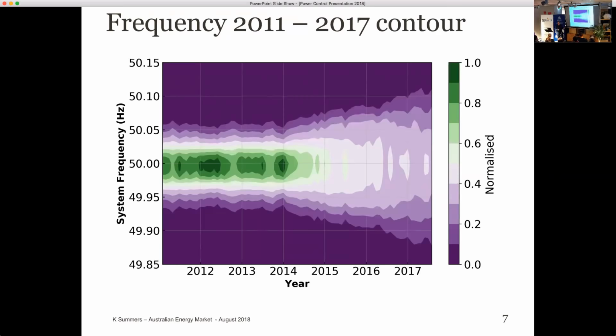So they're following them and ignoring their governors. Now what does the governor do on a synchronous machine? It maintains its rotational speed close to its nominal rotational speed. That's what synchronism means - we set a nominal rotational speed and all synchronous machines should behave such that they maintain synchronous speed.